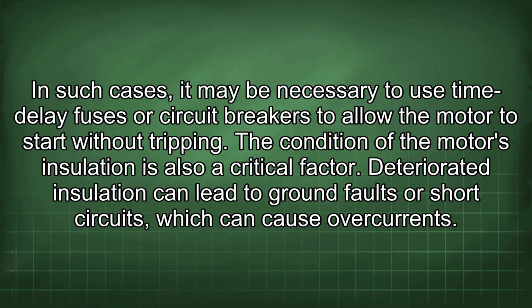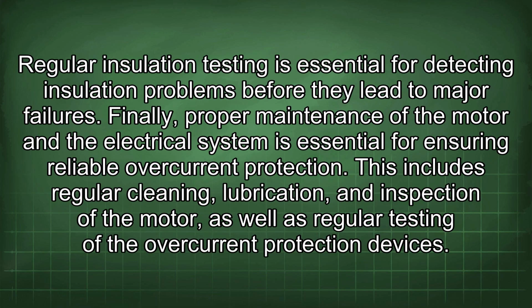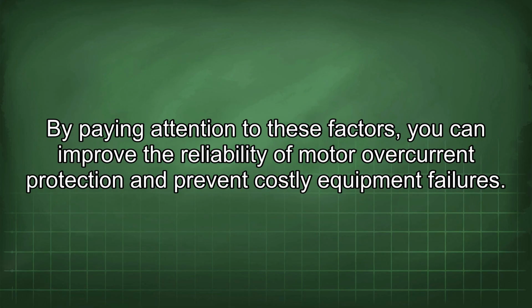The condition of the motor's insulation is also a critical factor. Deteriorated insulation can lead to ground faults or short circuits, which can cause overcurrents. Regular insulation testing is essential for detecting insulation problems before they lead to major failures. Finally, proper maintenance of the motor and the electrical system is essential for ensuring reliable overcurrent protection. This includes regular cleaning, lubrication, and inspection of the motor, as well as regular testing of the overcurrent protection devices. By paying attention to these factors, you can improve the reliability of motor overcurrent protection and prevent costly equipment failures.